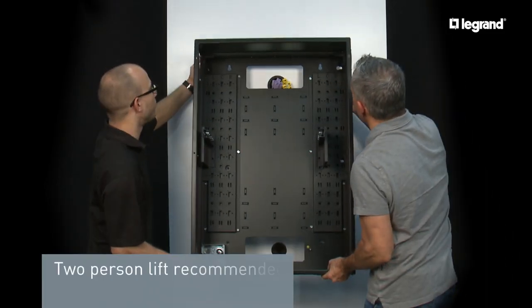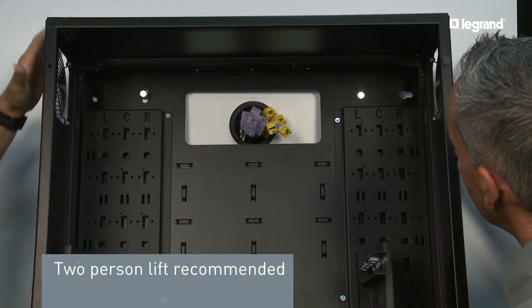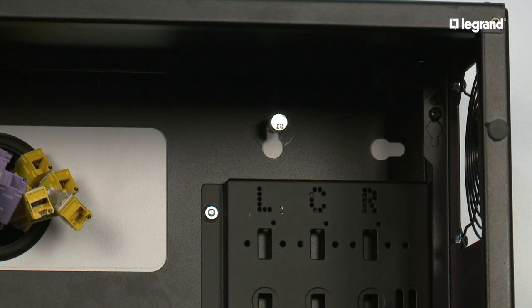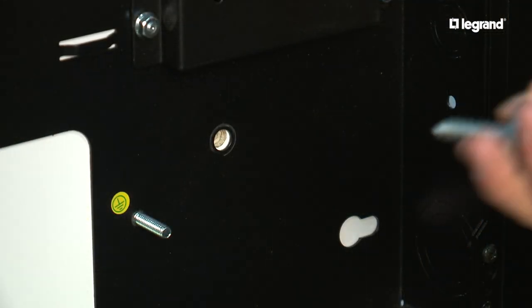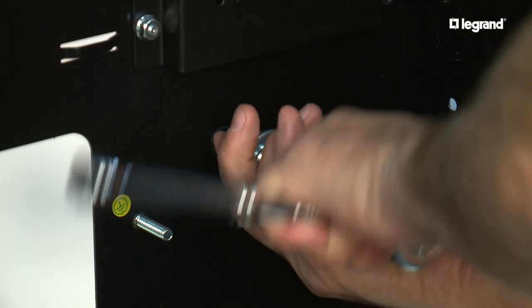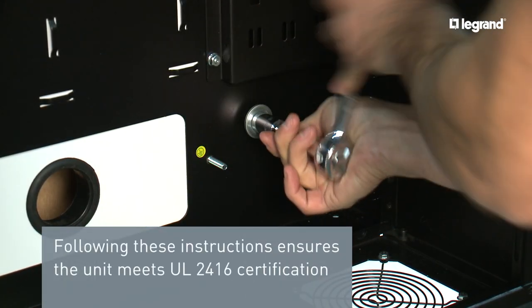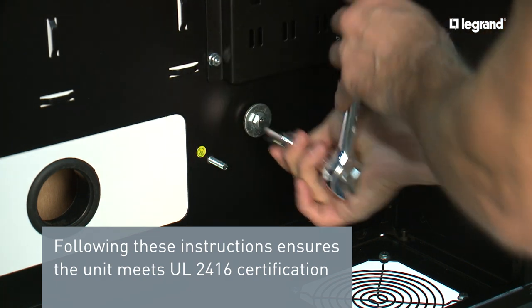Lift the unit into place. Align the 2 top bolts to the top keyholes in the unit. Install the bottom 2 bolts and tighten all 4 bolts. Following these instructions ensures that the unit meets UL2416 certification with a 150-pound rating.